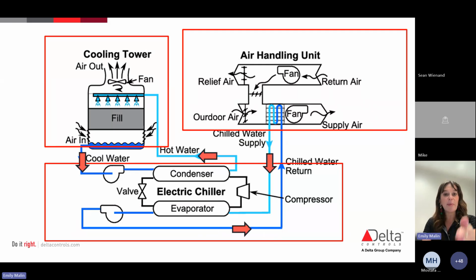And the way that this is happening in this scenario is that all of that water is flowing through each one of these different areas, and throughout, you're seeing water flow sensors. Is the water enough? Is it moving enough? Is the pressure enough? What is the temperature? And throughout this, you're always getting those little checks and balances to make sure that you're getting that desired temperature in those zones themselves. And again, if it is, then you want to be able to turn those off to save that electricity or to save that energy.